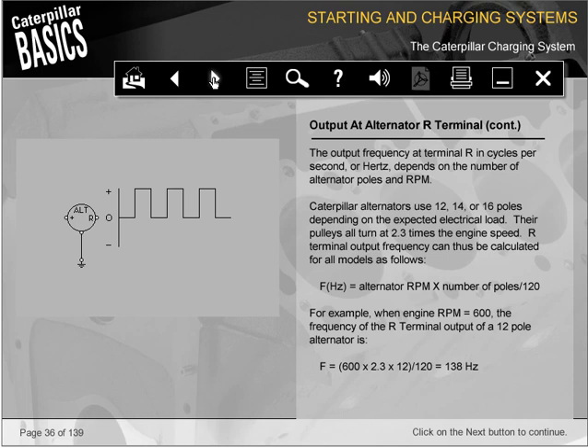The output frequency at terminal R in cycles per second, or hertz, depends on the number of alternator poles and RPM. Caterpillar alternators use 12, 14, or 16 poles, depending on the expected electrical load. Their pulleys all turn at 2.3 times the engine speed. R terminal output frequency can thus be calculated for all models as follows.